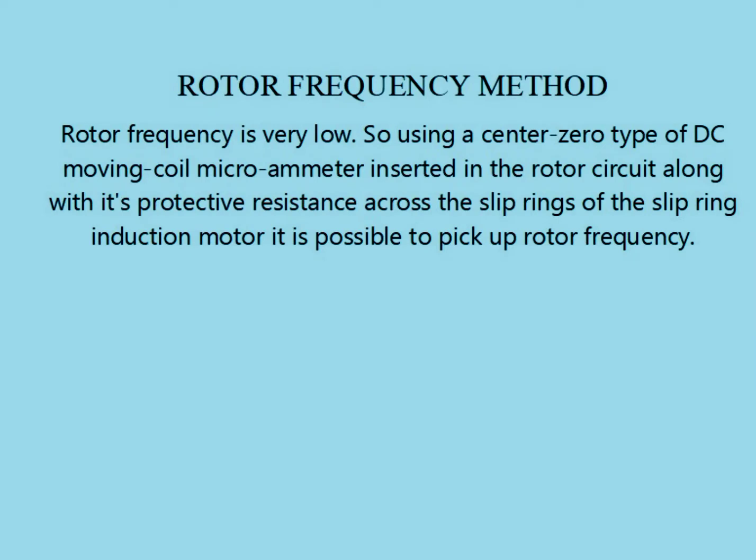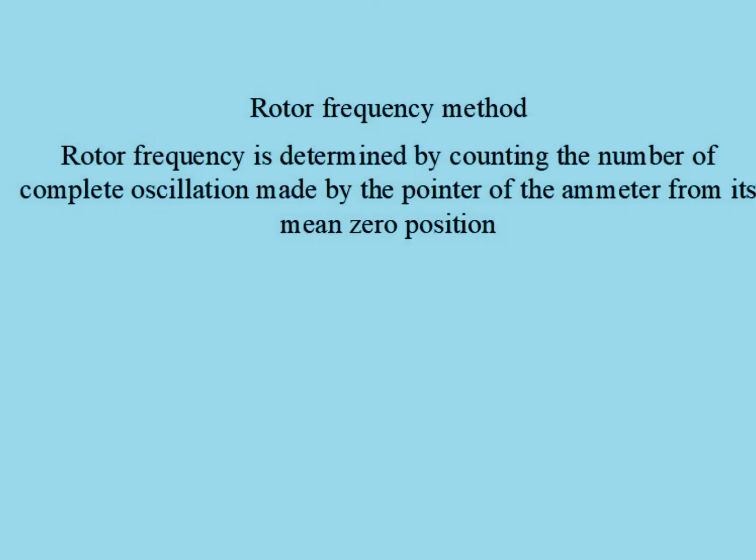The second method is by using the rotor frequency method. Since the rotor frequency is very low, the frequency can be found by inserting a galvanometer in the rotor circuit. In our case, we have used a center zero DC microammeter as a galvanometer. Then the rotor frequency can be determined by counting the number of complete oscillations made by the pointer of an ammeter from its zero position.